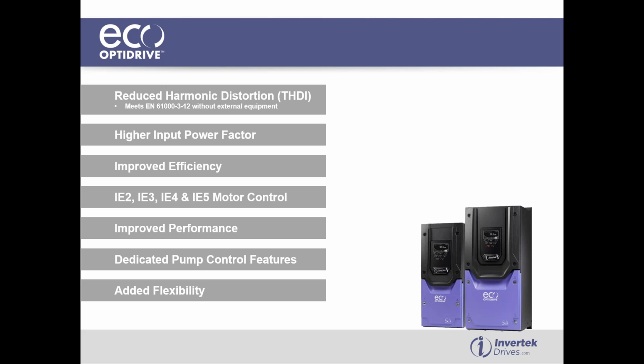We've also got inbuilt into the drive a function block editor, so we can actually customize, or the firmware is more customizable for OEMs which have specific functionality. We can also display real units on the display of the drive, so bar, PSI, degree C, parts per million, those kind of units that are normally seen in the industrial markets where these drives are used.